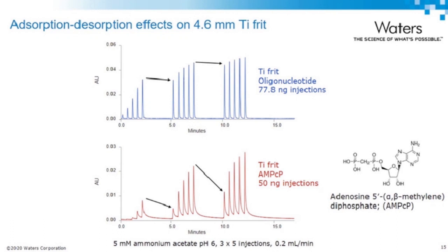That is because this sample conditioning is removed by the mobile phase that desorbs the analyte. So this chromatogram neatly shows and explains why you can see tailing peaks for those sensitive analytes in chromatography, because the adsorption on the frit happens and then the material could be slowly released from the frit. If you think about it, it also neatly explains the carryover effect.